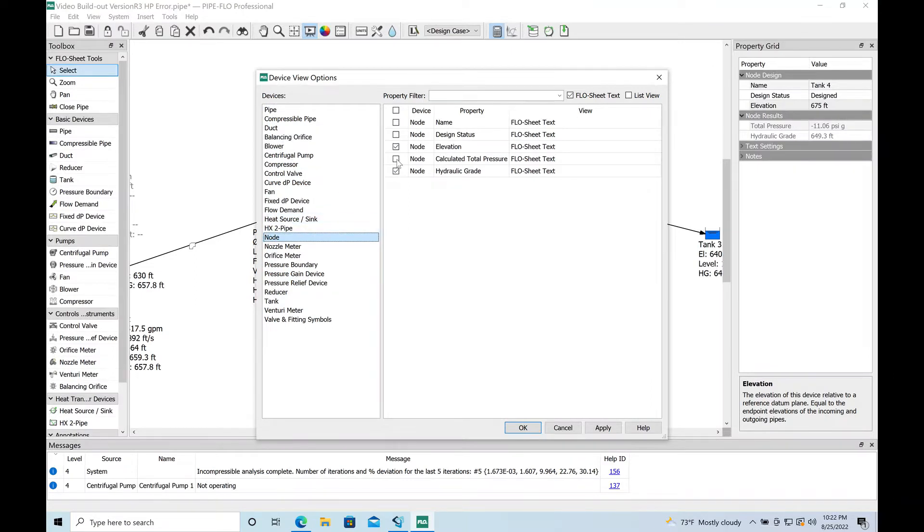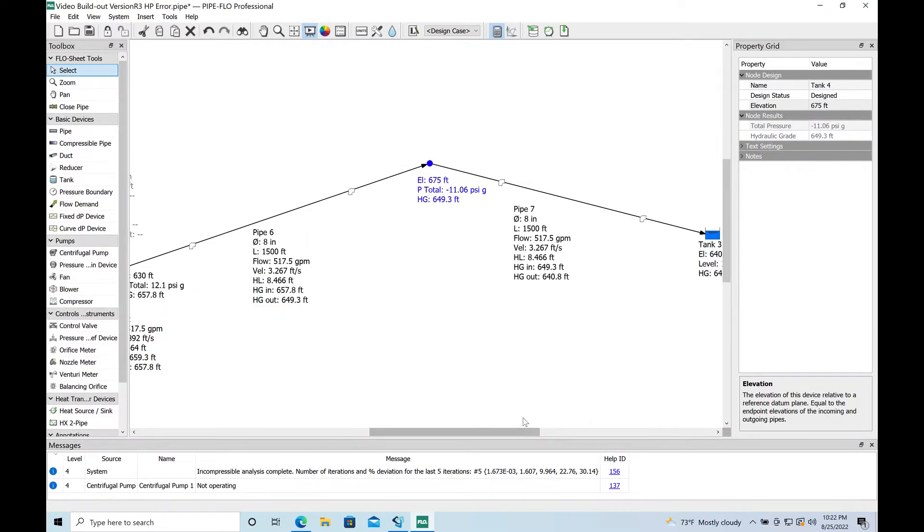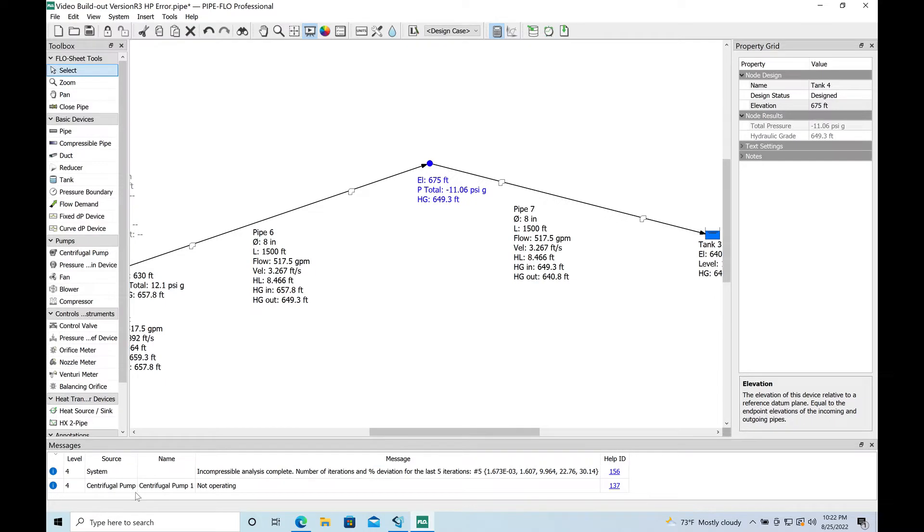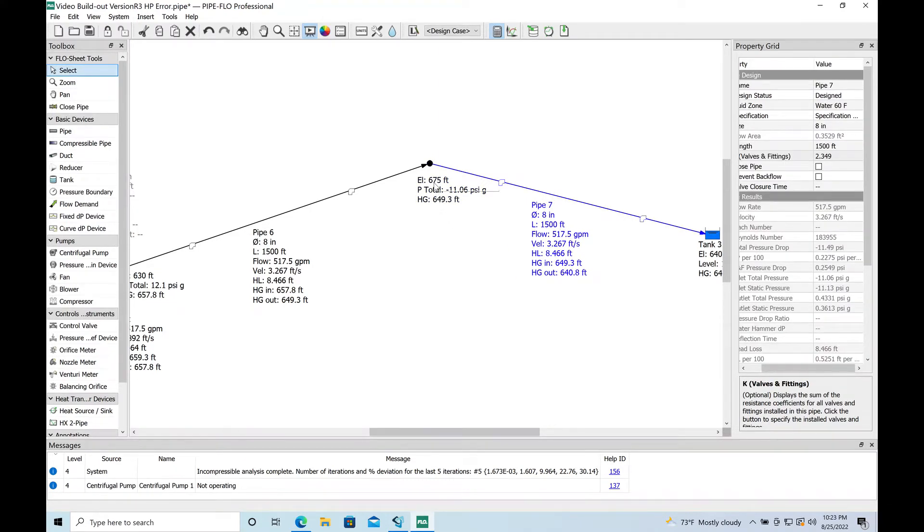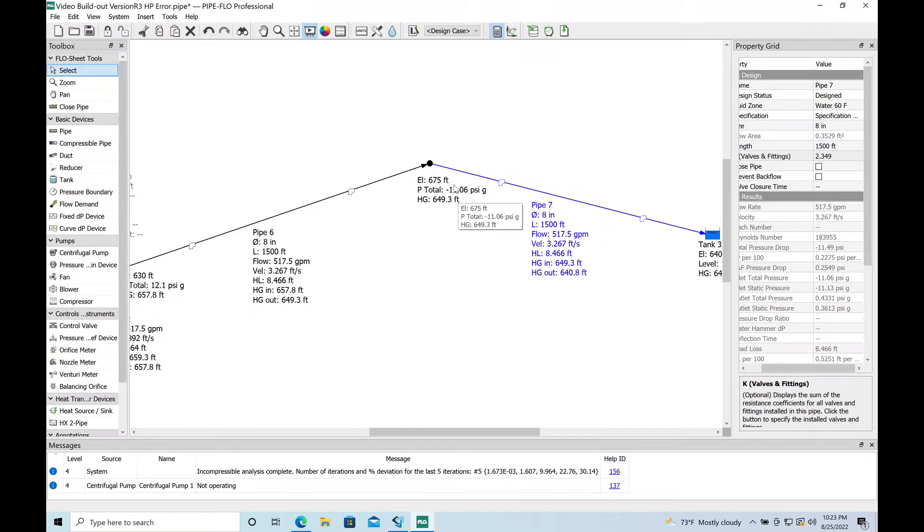You always want to know what your total pressure is at each node, and now you can see what the problem is. What's tricky is this did not give me any warnings down here to tell me that this was negative pressure. The model doesn't know, it's dumb, and basically it just let the hydraulic grade line go under the actual pipe node here. So this is something to watch out for and could have pretty scary effects on your model.